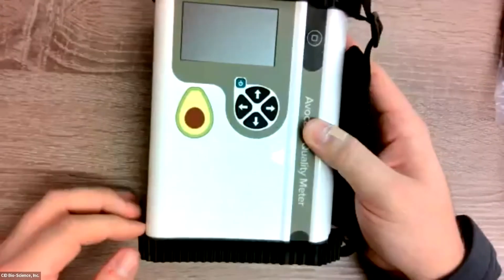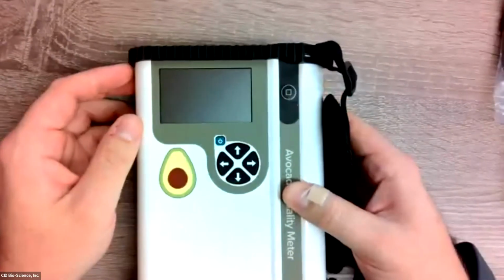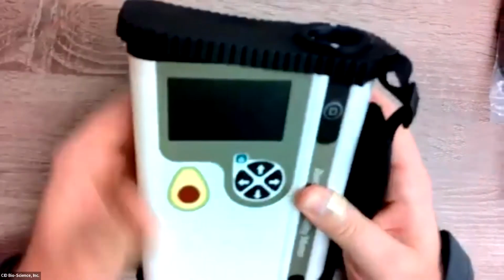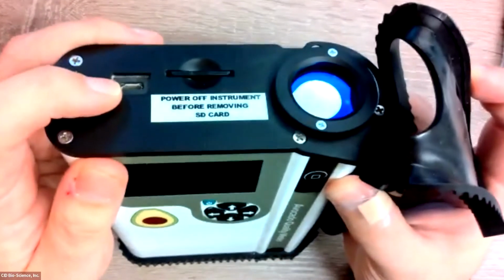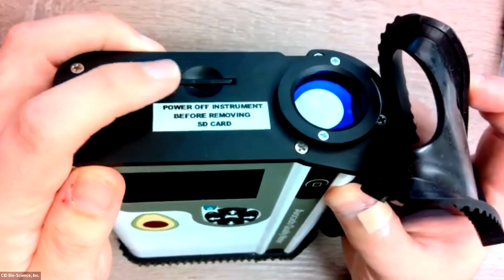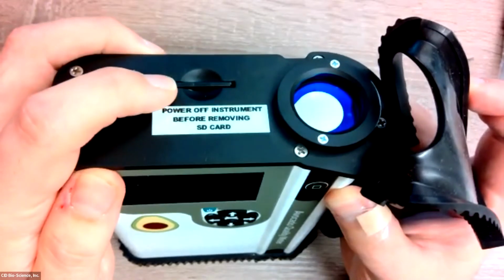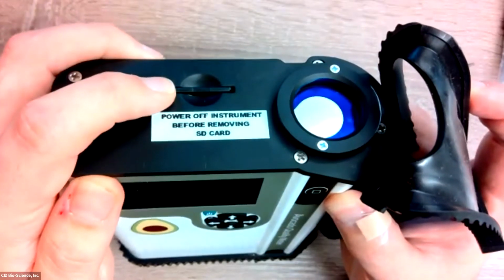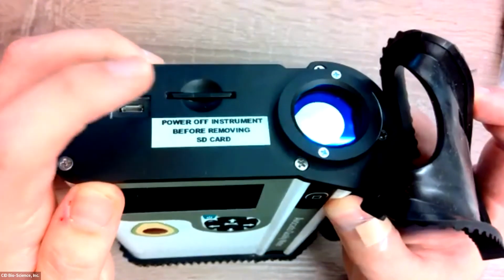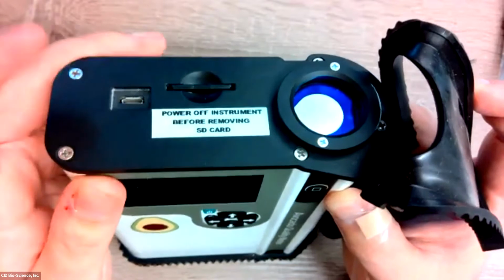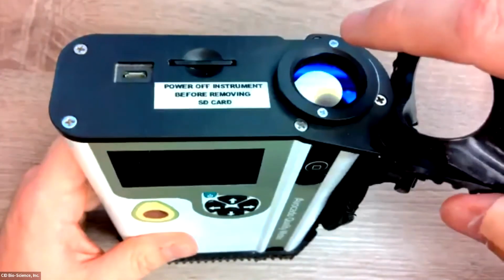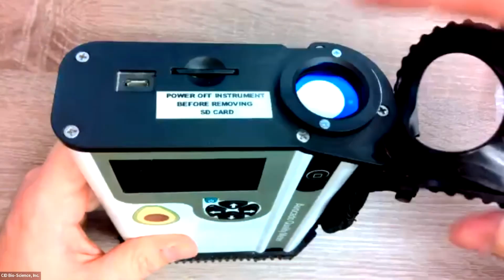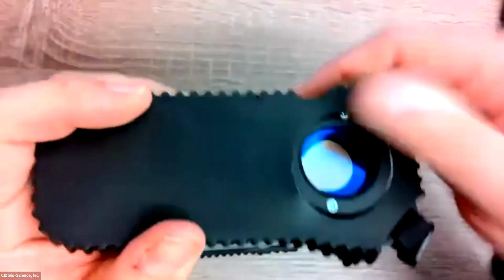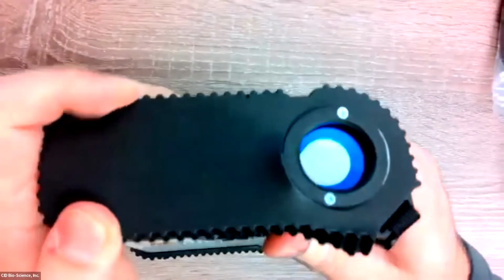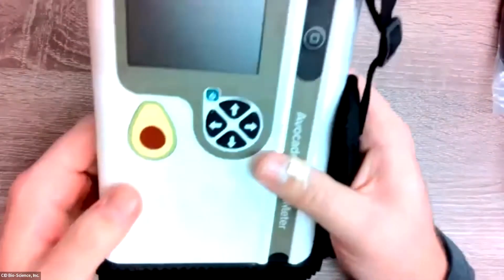The top and bottom rubber bumpers on the device can be removed, and those reveal a couple key features. So when I remove the top bumper of the device, simply by pulling it off, you'll see that there's the USB mini port. That's for updating the firmware. This is the SD card slot. So this is where the data is stored, as well as where the applications live if you need to update your application with the models on it. And so that is where all that is hosted on this SD card. This is the lens where the actual measurement takes place. So to put that bumper back on, you just simply place it back on, stretch it back over the edge, and it snaps back on.